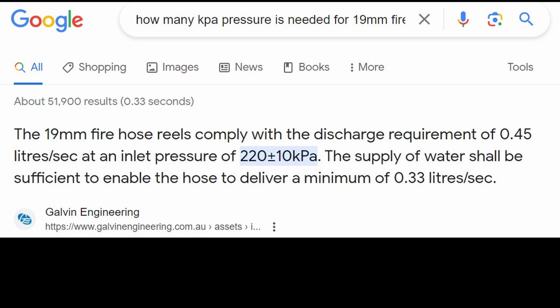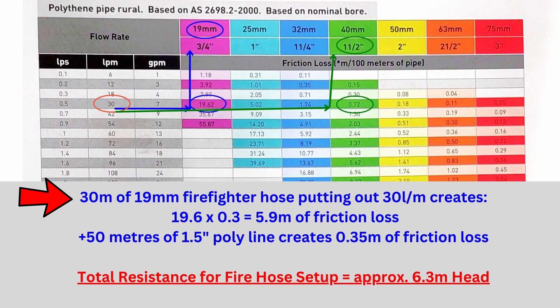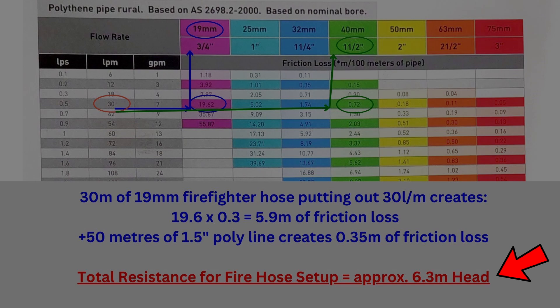A quick Google search shows that 220 kilopascals of pressure is needed for a firefighter hose, and we've already got 250 kilopascals in the system from the sprinklers, so that's more than enough. The flow required is 0.45 liters per second, which is just under 30 liters per minute. Going back to our friction loss chart: 30 meters of 19-millimeter firefighter hose putting out 30 liters per minute creates 19.6 meters of head per 100 meters, which equals 5.9 meters of total friction loss. And the 50 meters of poly pipe leading up to that hydrant point adds another 0.35 meters of head of friction loss, giving a total resistance of 6.3 meters of head for the firefighter hose setup.